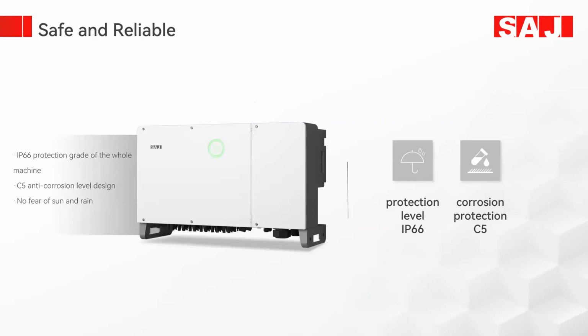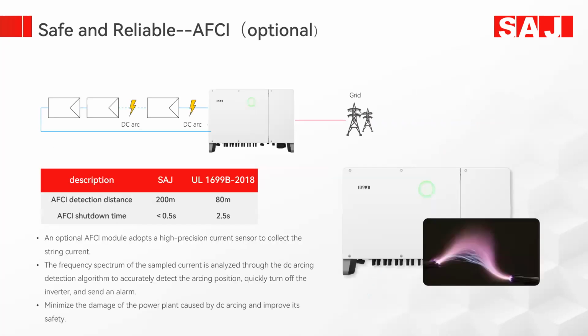When we talk about safety and reliability, it is a safe and reliable product. The whole machine has an IP66 protection grade and C5 anti-corrosion level design, no fear of sun and rain. Protection level is IP66 with C5 corrosion protection, and AFCI is optional: if there is some DC arcing, the inverter detects the arc in less than 0.5 second and turns off. The optional AFCI module adopts a high precision current sensor to collect the string current. The frequency spectrum of the sampled current is analyzed through the DC arcing detection algorithm to accurately detect the arcing position. It quickly turns off the inverter and sends an alarm, minimizing the damage to the power plant caused by DC arcing and improving its safety.